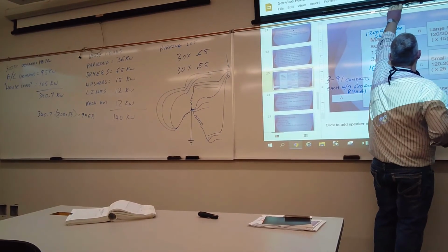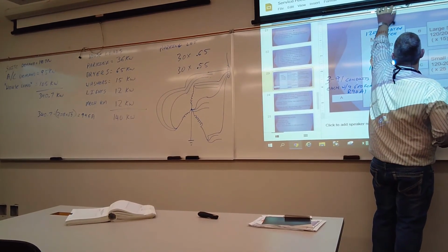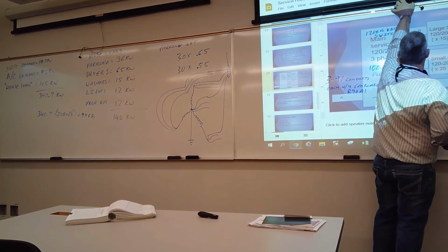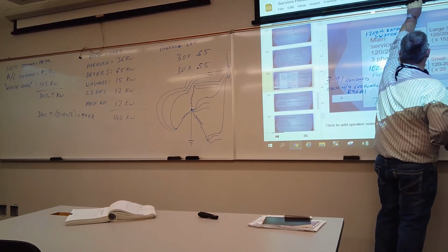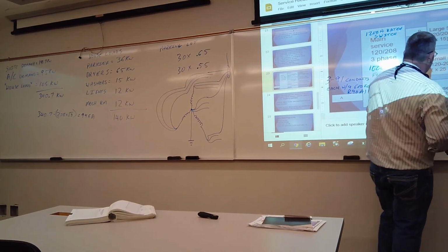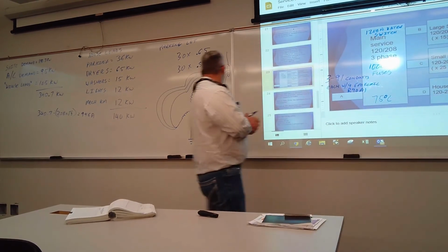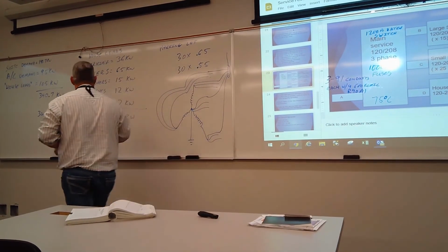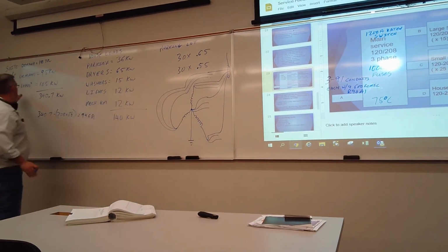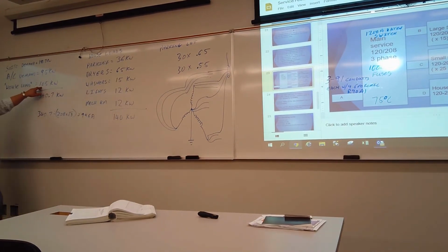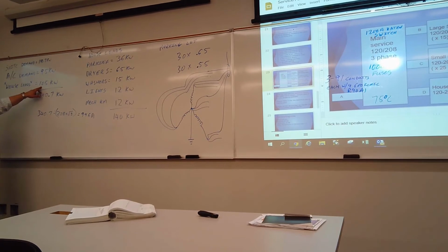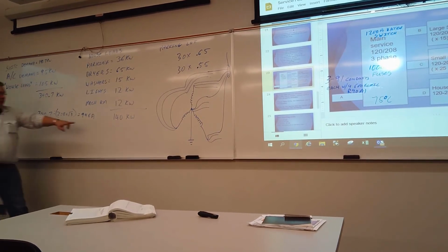Here, we're gonna start at the bottom and work our way up, just because frickin' string is driving me nuts. Our house panel. We calculated out our demand on that house panel of 140, we'll multiply by 75 to get 105 kilowatts, right? I told you to remember this number.